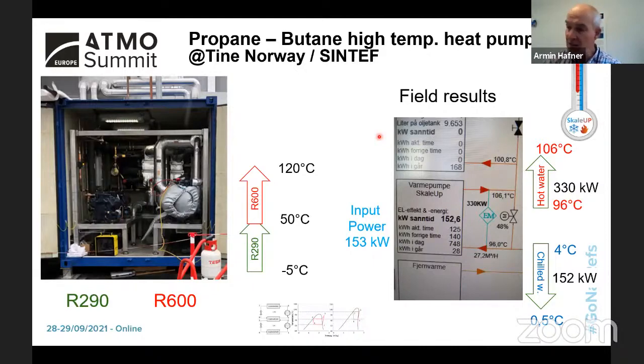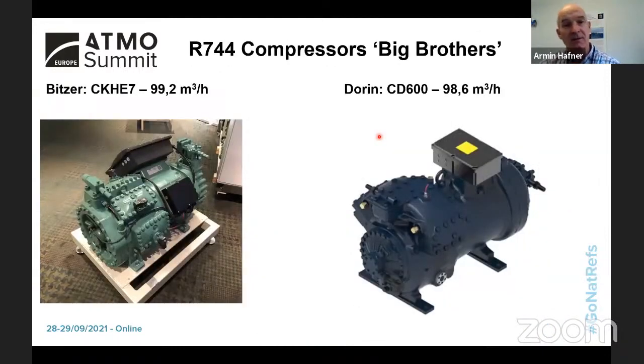heat pumps. We also see that in CO2 systems, the big brothers have arrived. Big brother means the biggest compressors now from Bitzer and Dorin are up in the range of around 100 cubic meters an hour. This is really what the market has been looking for a long time. Now it is possible to build systems up to above the megawatt size with a decent number of compressors. This is what industrial refrigeration needs. This is very good news, and thanks to Bitzer and Dorin and the others, providing a wider range of high efficiency compressors, which enables CO2 to enter even more markets.